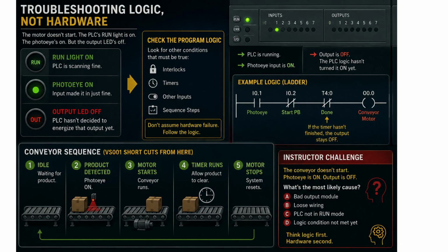The answer is the program logic, not the wiring, not the output module, not yet anyway. Run light on means the PLC's scanning fine. Photo eye on means the input made it in just fine too. But the output LED being off means the PLC itself hasn't decided to energize that output yet. That points to the logic. Maybe another interlock, a timer, some second condition that hasn't been met. Not a hardware failure downstream.